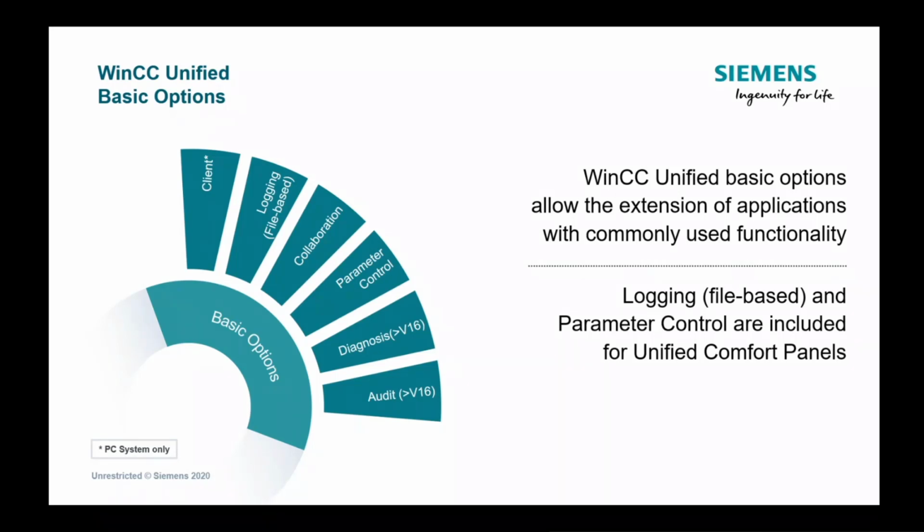But of course, it's a basic option, so we could scale it up. You might say, well, my customer wants another 10 clients. You can just buy a license for another 10 clients and apply those directly to your base system. We also have logging. WinCC Unified on the panel and PC-based platforms supports SQLite, so we can do file-based logging. It's included with the product, and a very, very powerful logging concept. And it's a seamless concept in terms of scaling up to a full relational database. We use the same schemas, so you can move from one to the other.